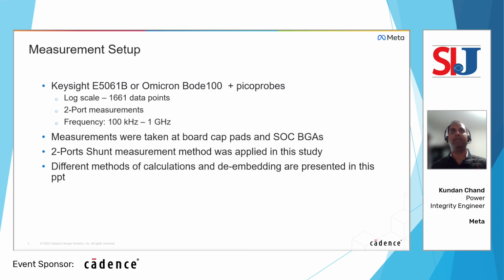And we tried both of these equipments, and we used the small Pico probes to access those tiny pads on the board, or BGA pads or capacitor pads, and the probes were used in conjunction with both the Keysight as well as the Bode 100.